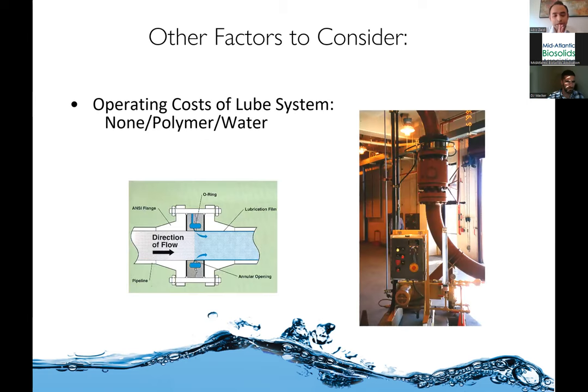Another factor is that when you select PC pumps or piston pumps, any kind of pump, and you're using a pipeline, if your pump cannot handle the back pressure in the pipeline, sometimes you need to add a lot of polymer or water in the line to reduce the back pressure. Adding some water, I can understand, but adding a lot of polymer is actually counterproductive sometimes, because you just dewatered from, let's assume, 2% to 25%.